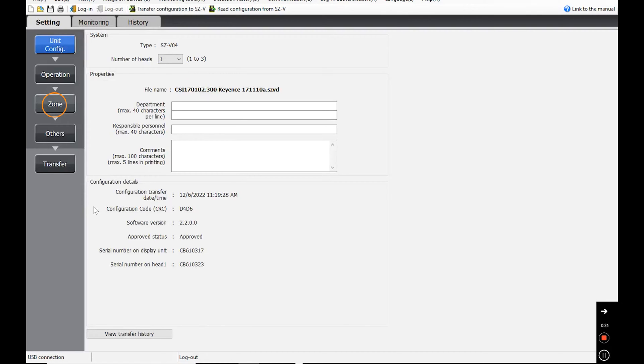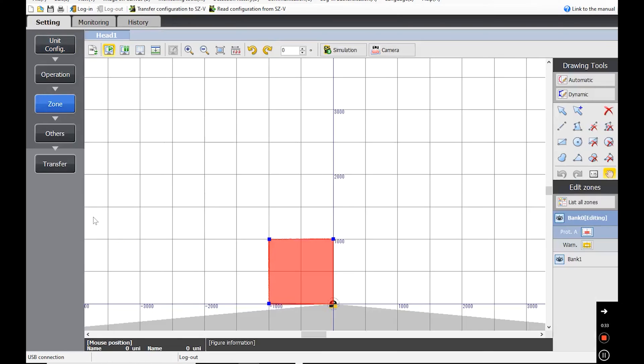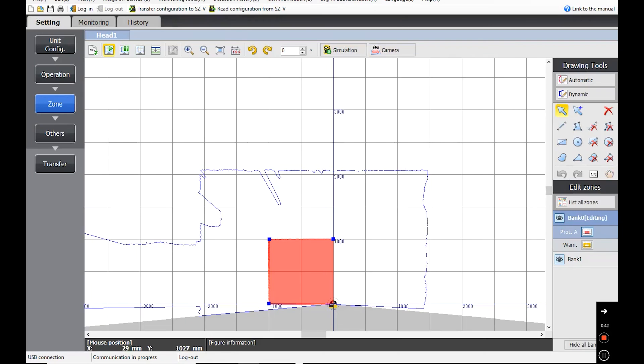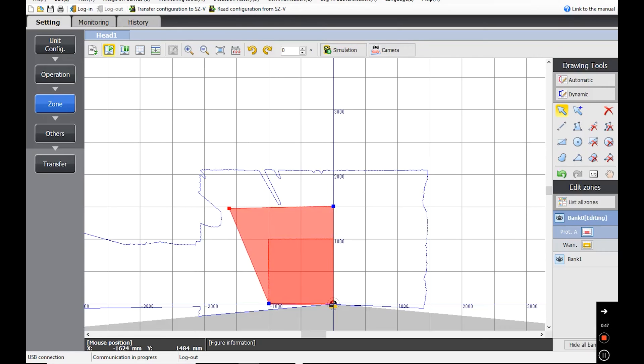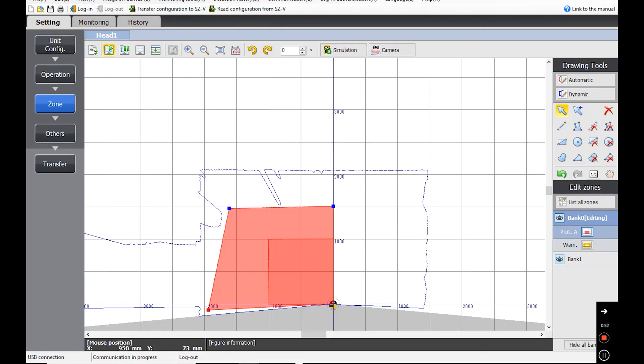Press Zone. Next, select Bank Zero and use the arrow in the drawing tools. Drag and drop the points and set your custom scan zone. We do not recommend crossing over the other side of the axis towards the filter wall as overspray can prematurely stop the robot.